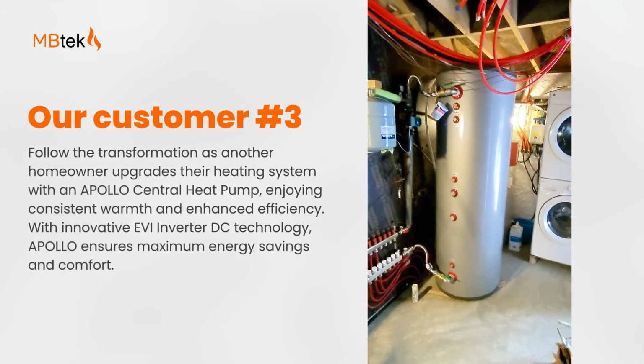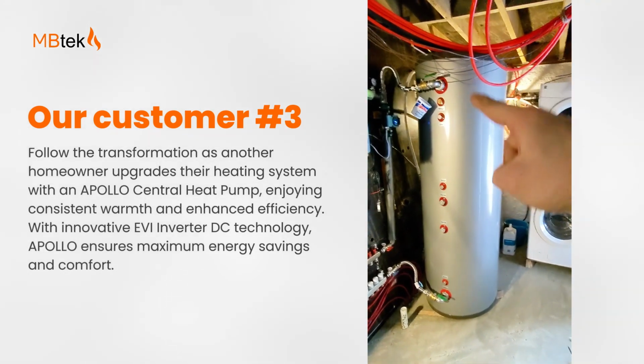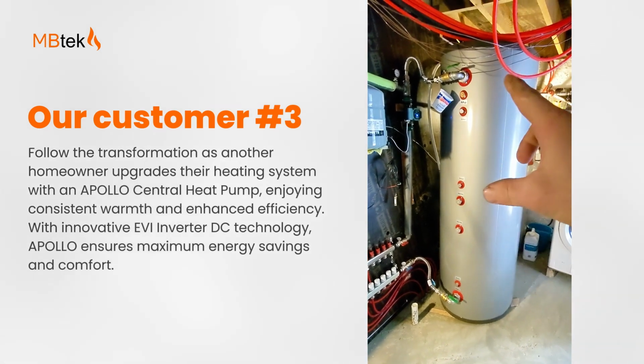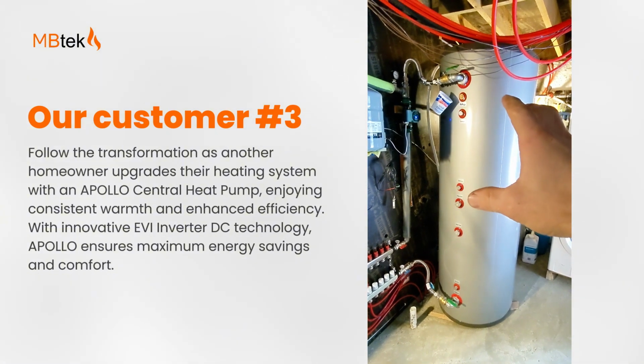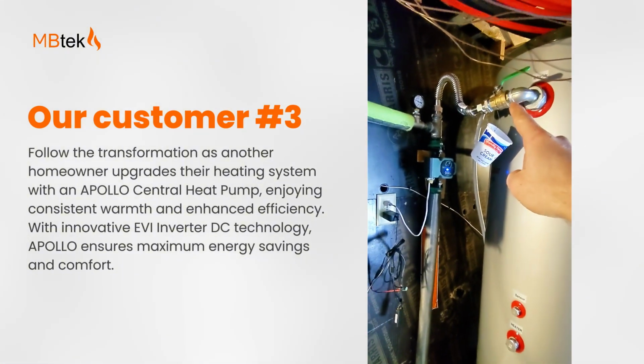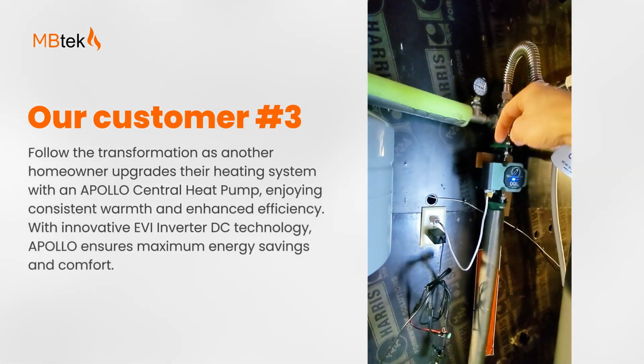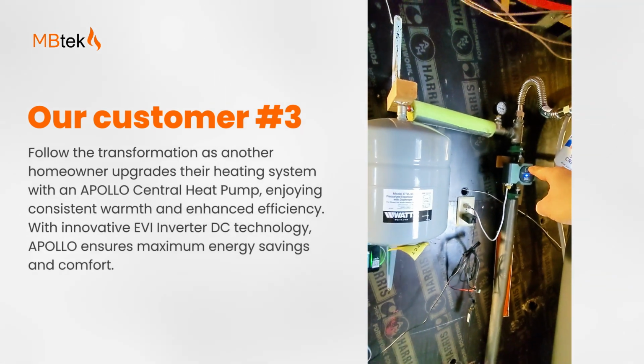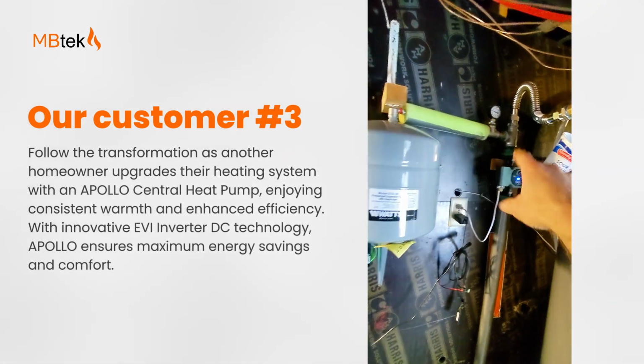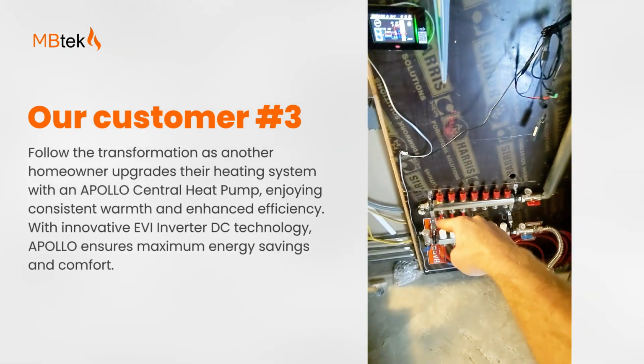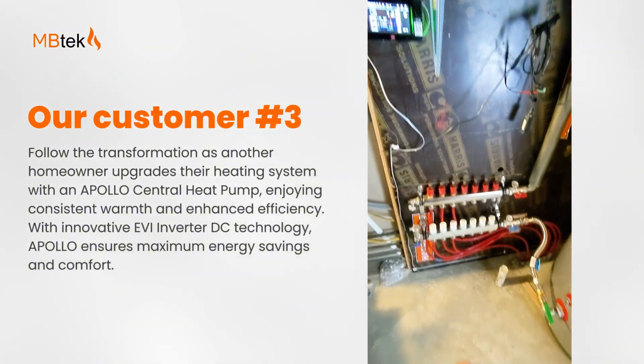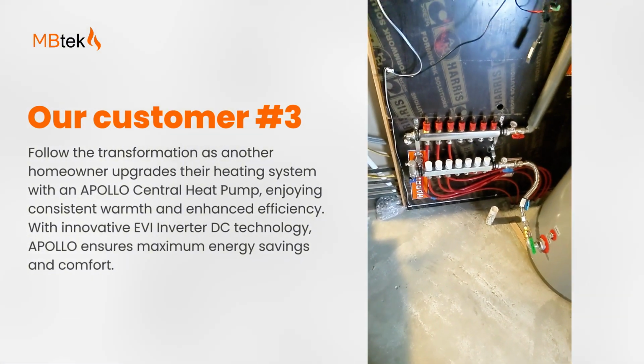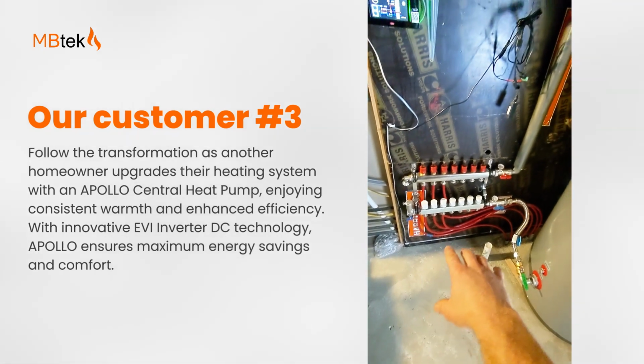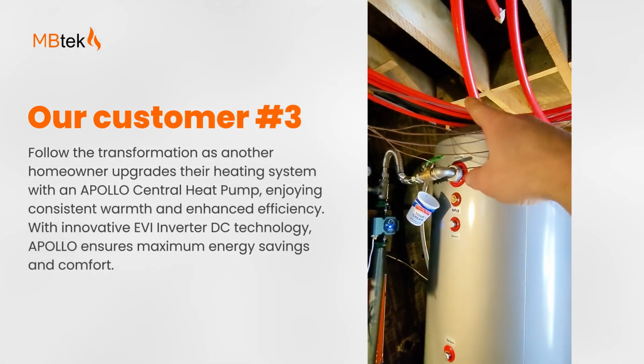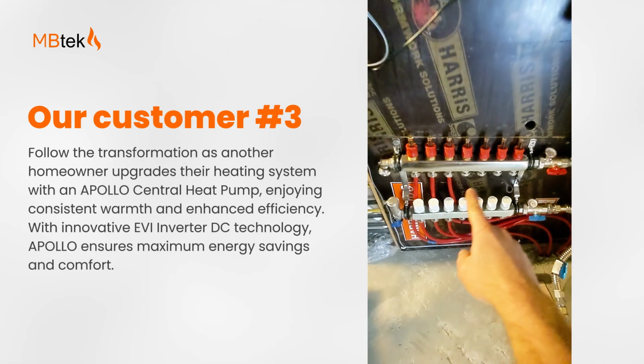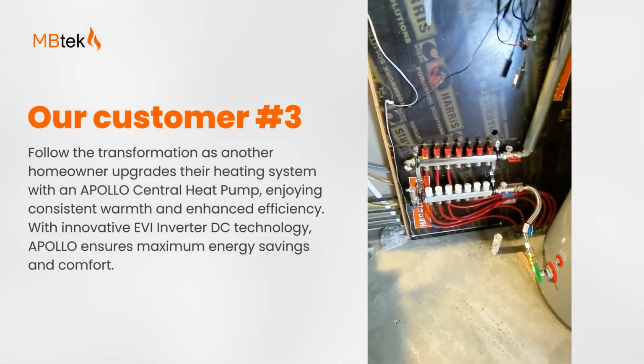Yep. So as mentioned before, inside the tank, apart from the heat exchangers, is just water, 130 gallons. That water is being sent through this line, coming through the circulator pump here, another expansion tank for that closed loop, and being distributed into the manifold and then into all the load sides, like the slab, and then later on the hydronic radiator panels that are being hooked up to the remaining connection ports of the manifold.